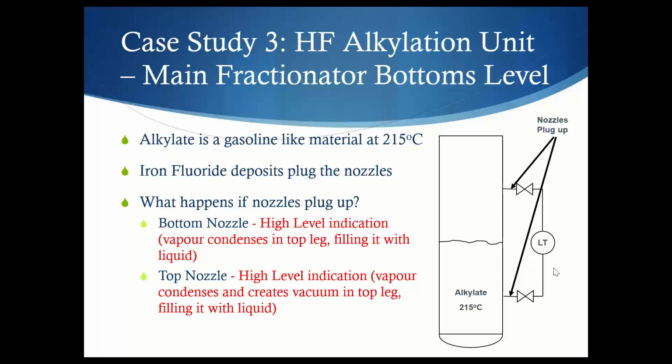Now that's not something that's that intuitive, you have to think through that. You may even have to find out from your own facility whether that's possible. But certainly if you get condensation, then you can get this vacuum effect, or you can get extra liquid going into the top leg that you wouldn't expect.